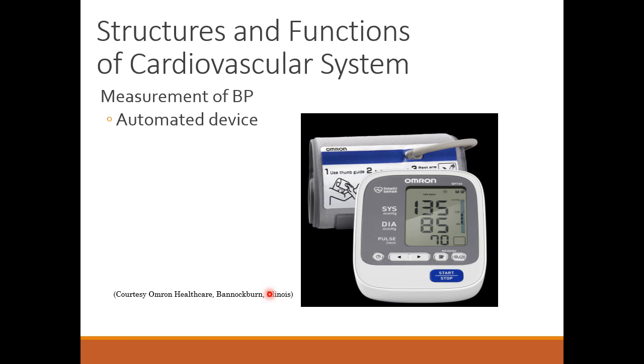That's why the manual backup is very important, because before you call a doctor, you want to make sure that you're letting him or her know that you checked it manually as well. Because unless you can make sure that machine is functioning perfectly, which you don't have any guarantee of, you'd want to check it manually. Also, for titrating medication, you don't want to be using an automated device for titrating something, especially long-acting medication.